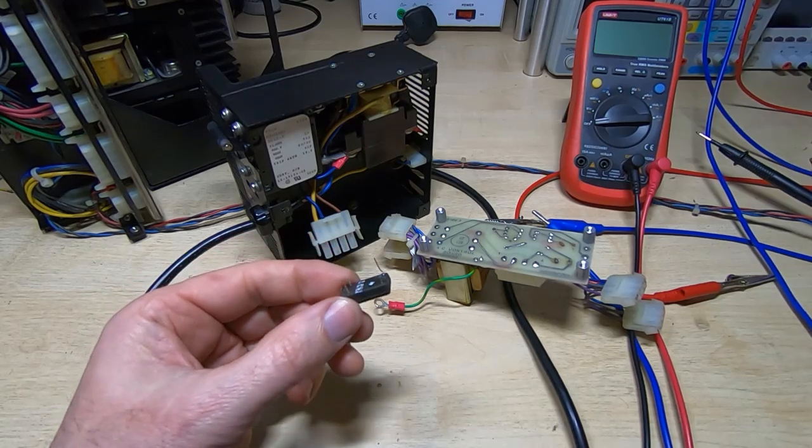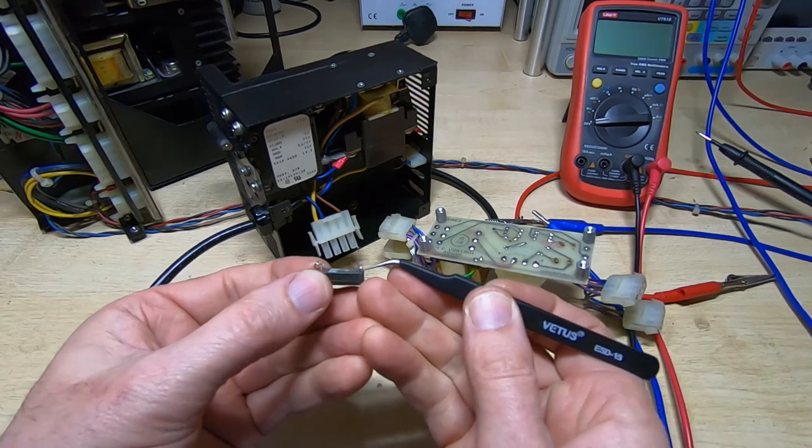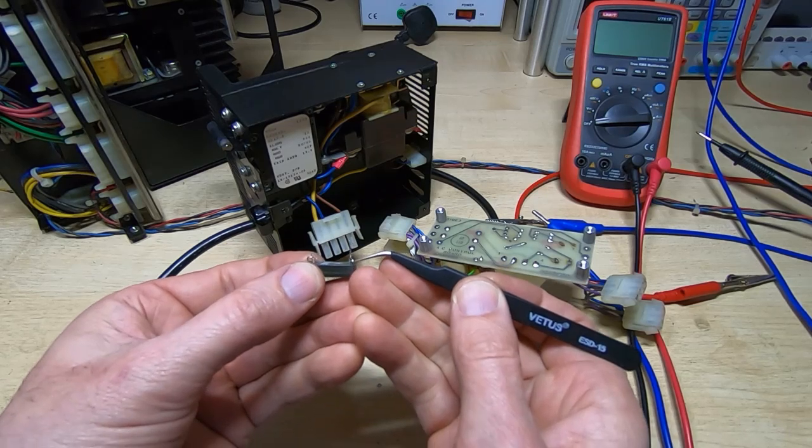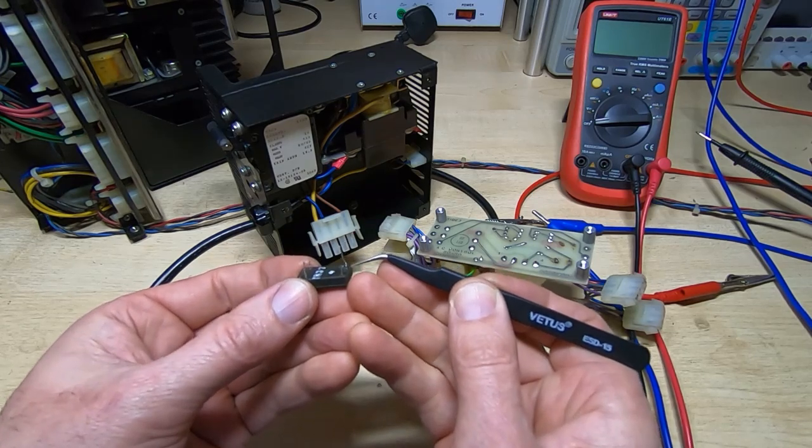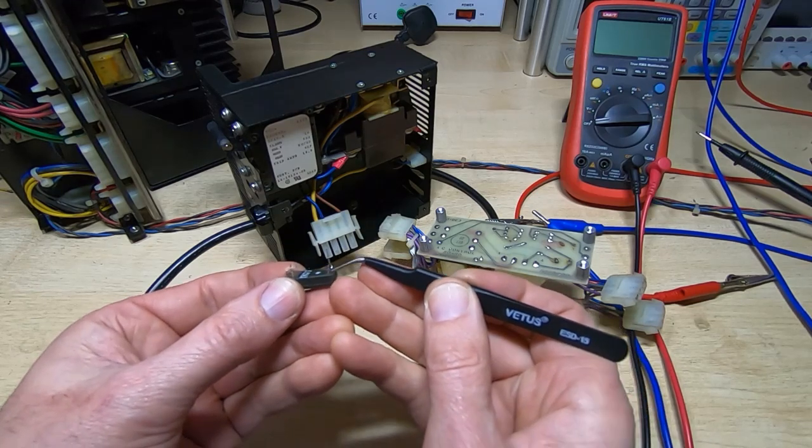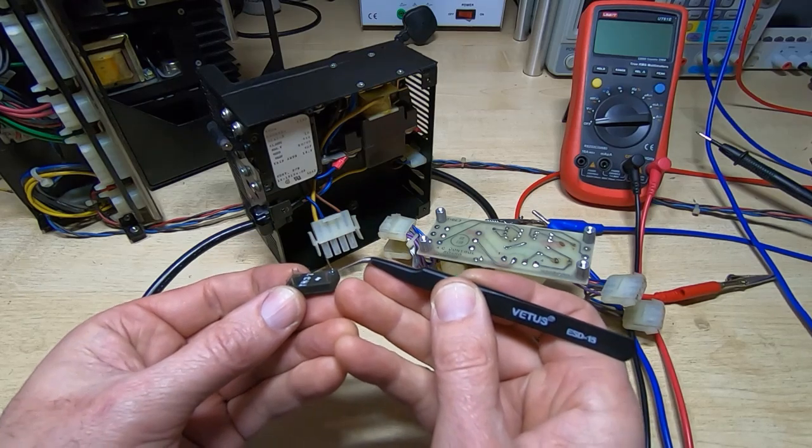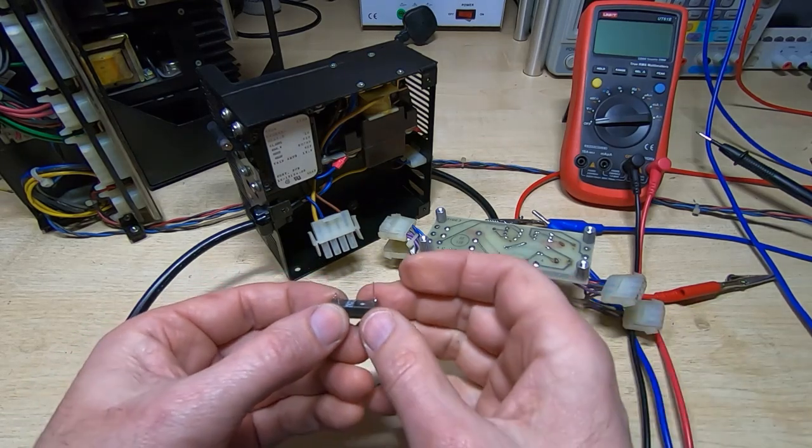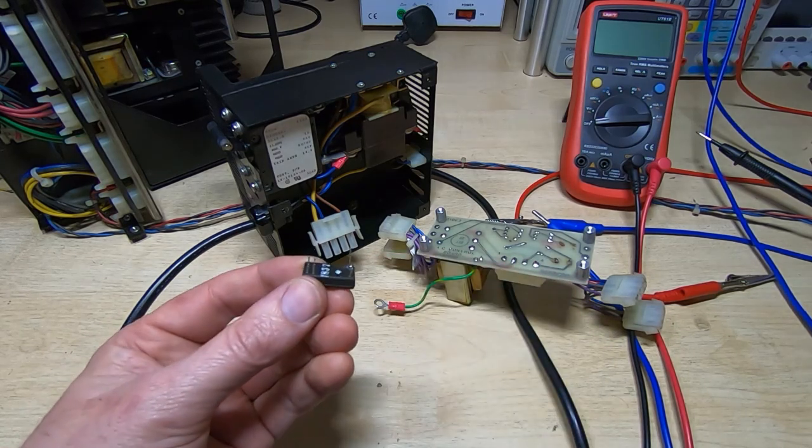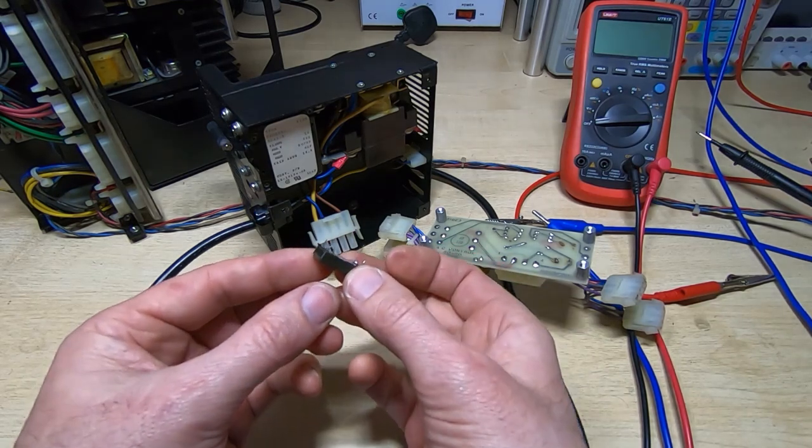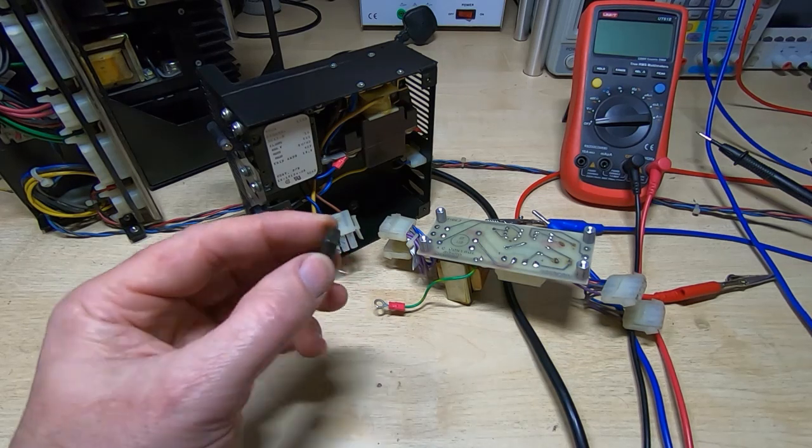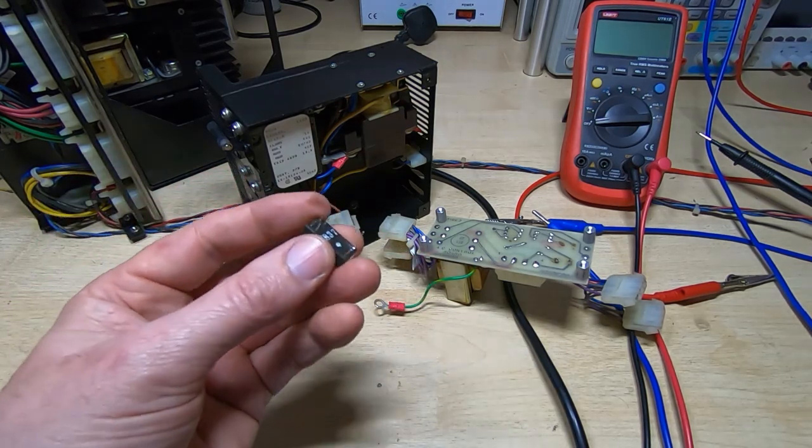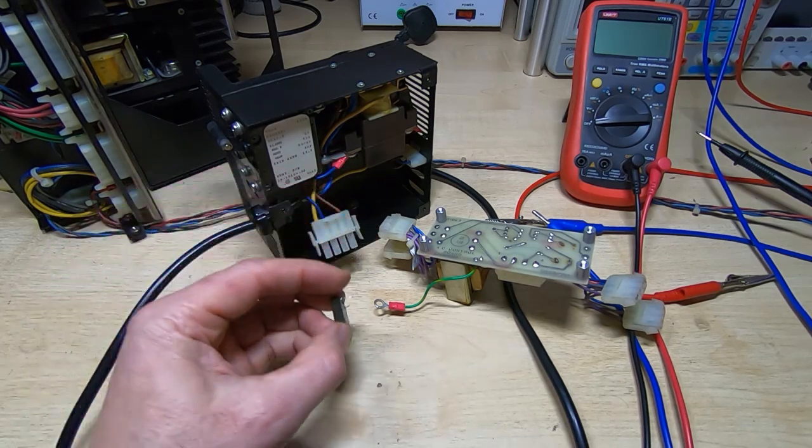OK, I had a look at this under the microscope and the pin had broken off flush with the case, but the case has kind of got an extrusion where the pin comes out. So it sits slightly proud of the PCB. And it's about a millimetre. So what I did was to get a very sharp knife and cut away that protrusion on the pin that had snapped off, went about another half mil deep, ended up with about one and a half mil of the pin sticking out. And that was enough to allow me to nice and firmly solder a new lead onto the device. I checked all the other pins and there's a bit of corrosion on there. That cleaned off with IPA. It doesn't seem to go too deep. So I'm going to try and reuse this one. They are quite difficult to get hold of and I didn't really want to modify the machine, if at all possible. So I'll get this resoldered to the board, clean it up and see if it's resolved the problem.